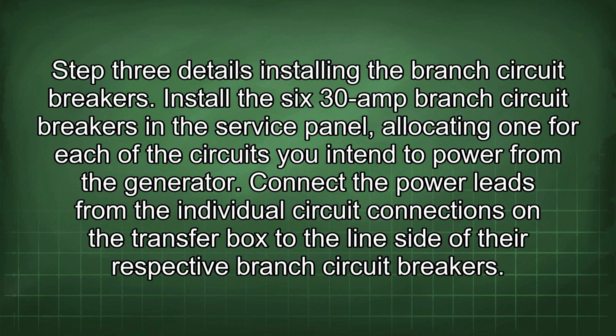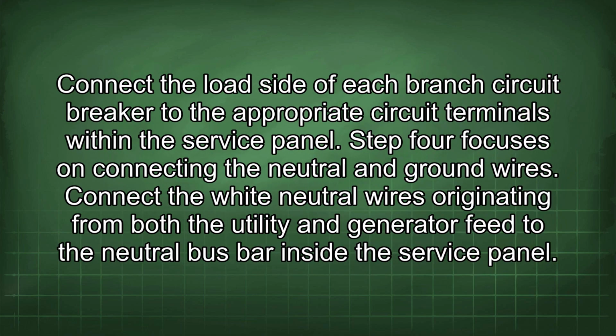Step 3 details installing the branch circuit breakers. Install the 6 30-amp branch circuit breakers in the service panel, allocating one for each of the circuits you intend to power from the generator. Connect the power leads from the individual circuit connections on the transfer box to the line side of their respective branch circuit breakers. Connect the load side of each branch circuit breaker to the appropriate circuit terminals within the service panel.